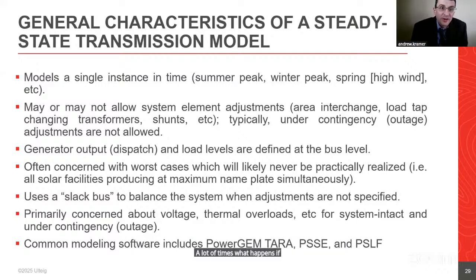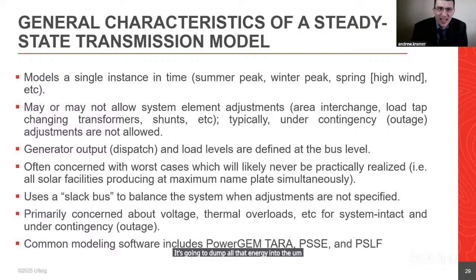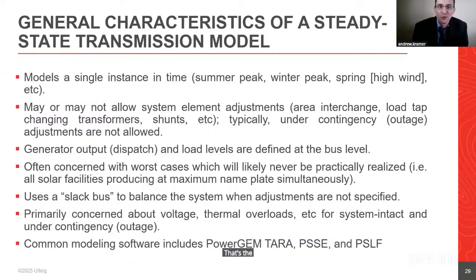A lot of times what happens if you're interconnecting a bunch of generators and you don't dial down the generators somewhere else to balance that, it's going to dump all that energy into the slack bus. I've reviewed models from other people where everything looks great, but ten states over where the slack bus is located, we've overloaded a line by like 5,000%. That's the sort of thing you want to avoid in this arena, and again, it's because the models don't really know what to do.